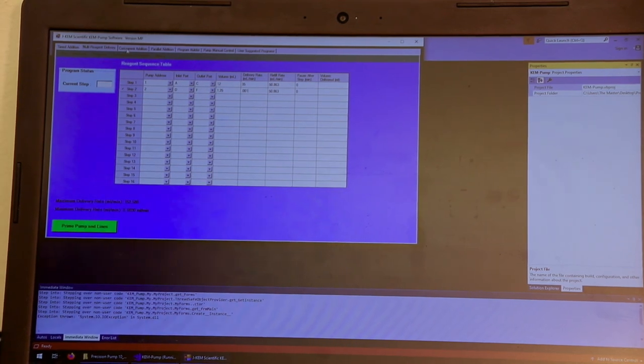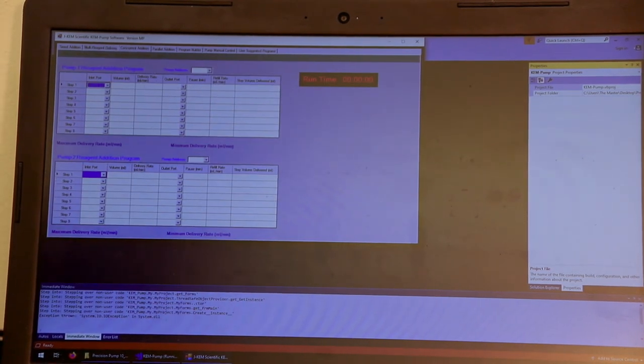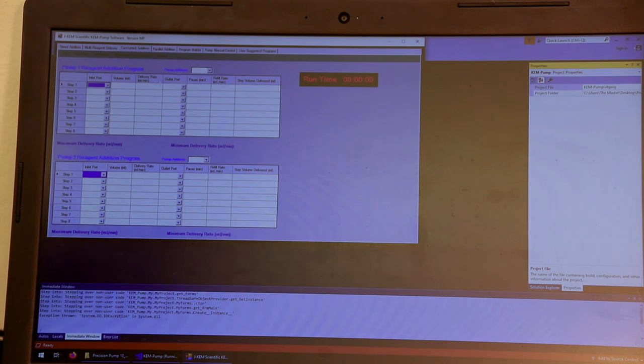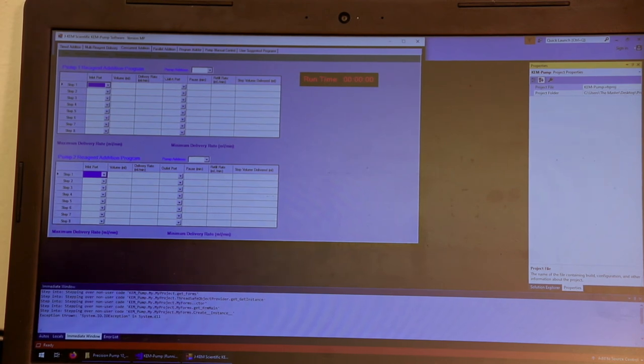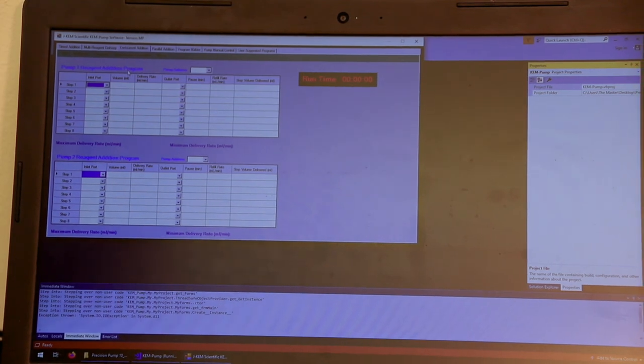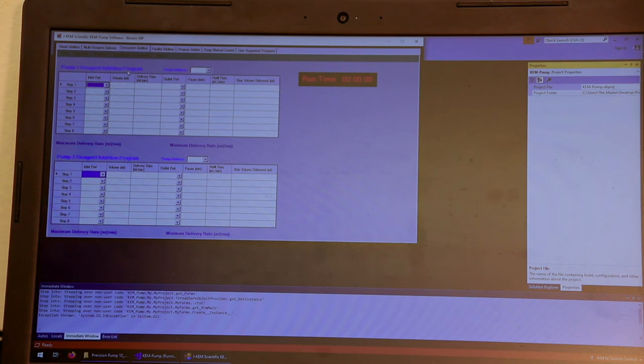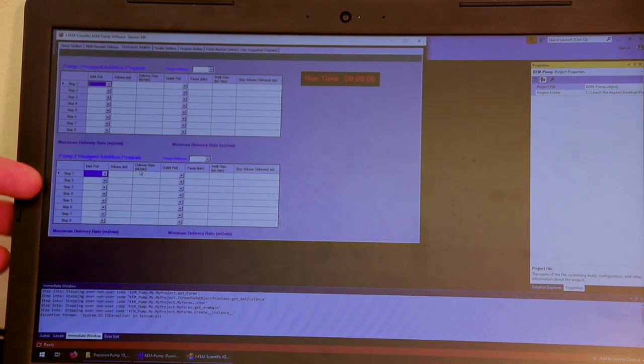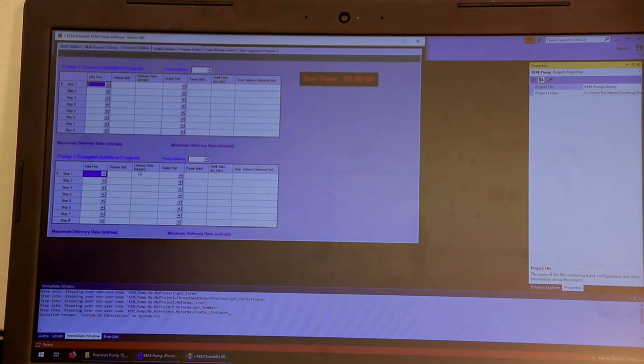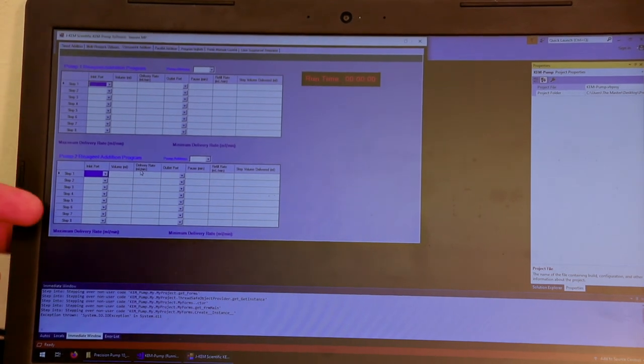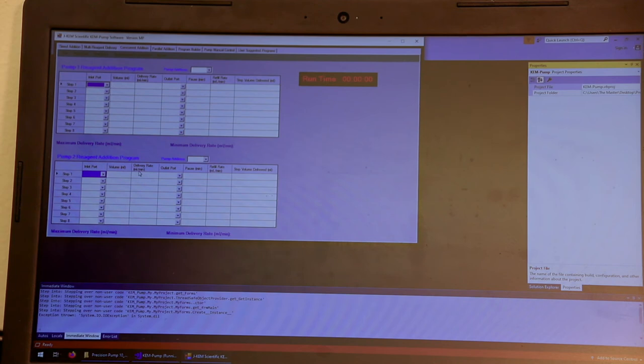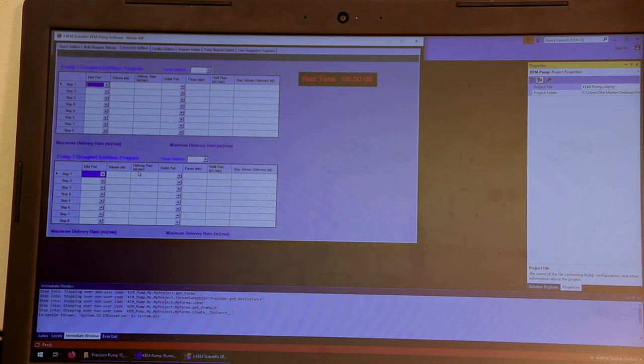The next experiment is called concurrent addition. And in this case, because I have two pumps, I can set up something similar. I can tell pump one to create an addition program for it, which would be what port to go to and fill from, what port to dispense to, the volume that it needs to dispense, and then its speed. So this would be an independent program for pump one. I would set up the same program for pump two or a different program for pump two. But now when I start this experiment, both pumps will simultaneously and in parallel run their individual, independent programs from one another.